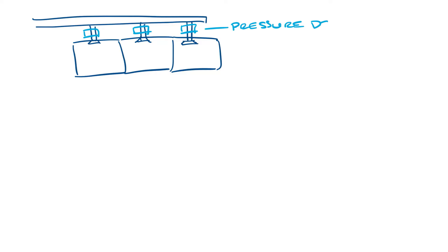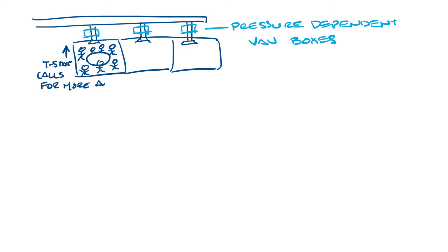Now let's look at pressure dependent VAV boxes. Pressure dependent VAV boxes in an HVAC system work in a similar manner. Let's say we have a conference room and a couple areas with pressure dependent VAV boxes. If the conference room goes from empty to full, the thermostat will tell it it needs more air and it'll call for the box to open the damper for the conference room. The offices on that same system will get less air because opening the damper on the conference room box changed the pressure in the system.